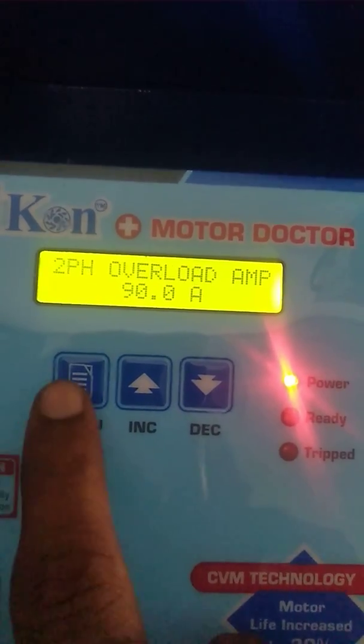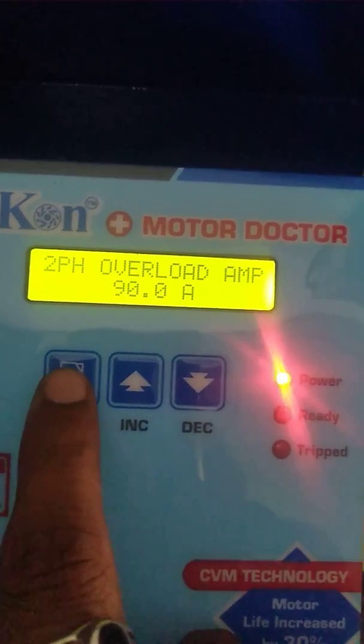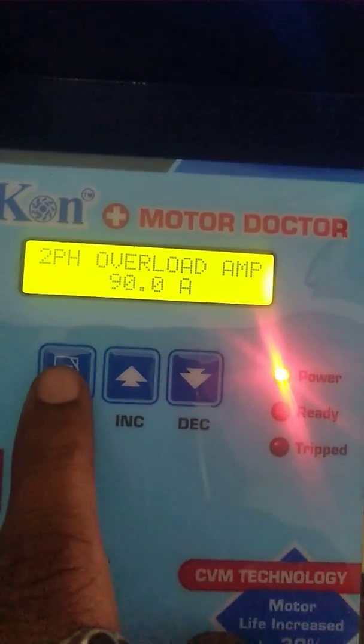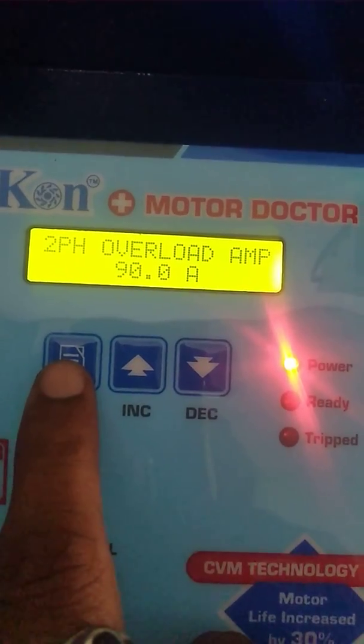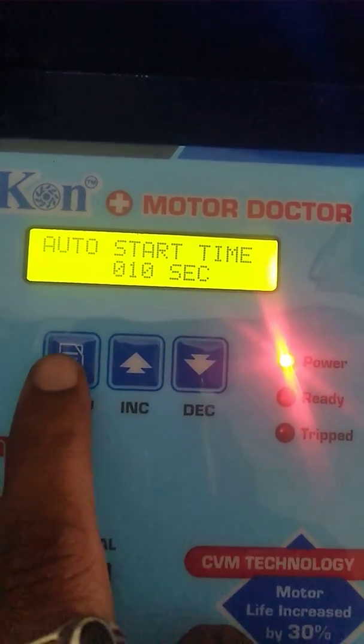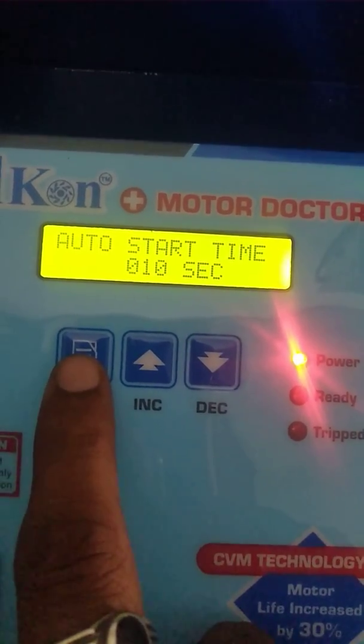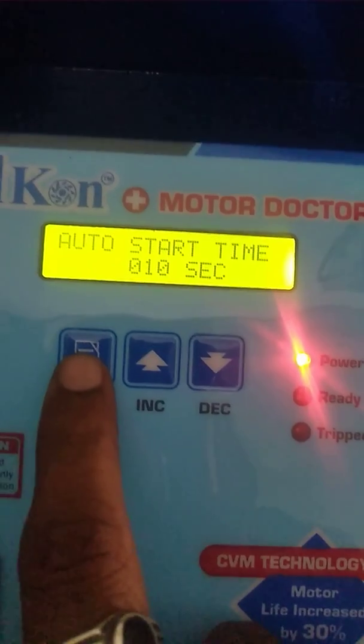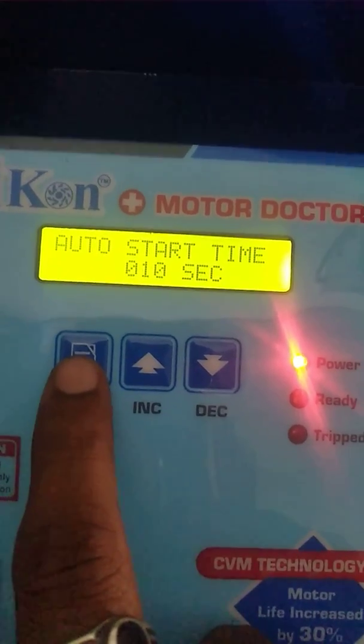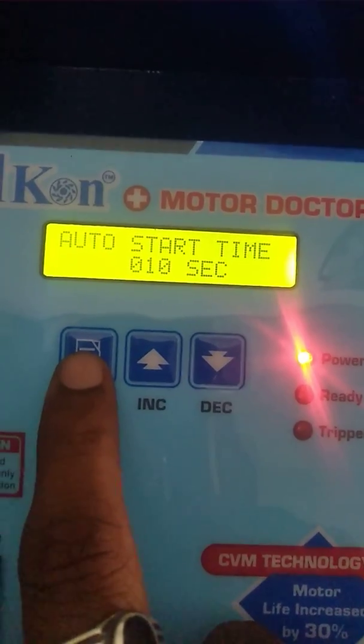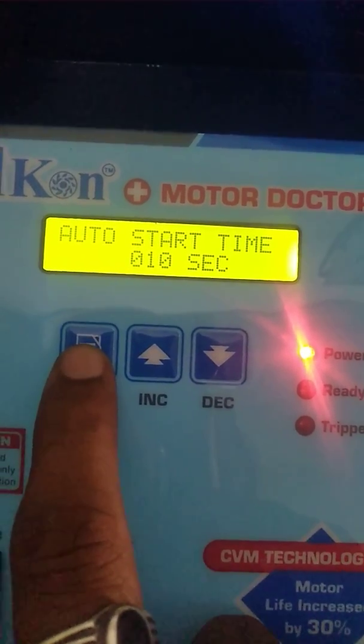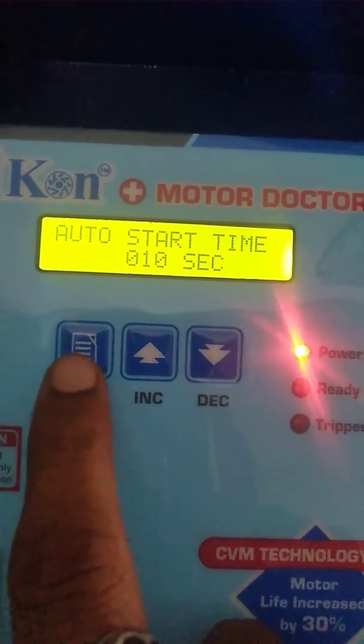If the amps exceed 90 amps, the controller automatically switches off the motor. Then the auto start time: once the power is switched off and then resumes, the motor starts automatically after 10 seconds. That is the auto start time.